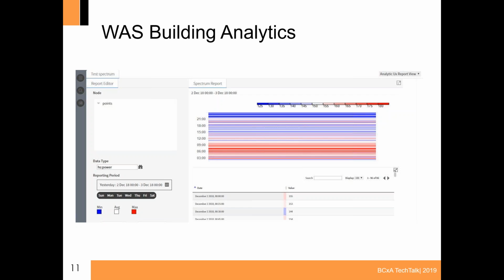And he pulled up another screen. Nope, they didn't override the system. All right. And I went from this screen. Unfortunately, I don't have screen captures for the other, but went through and said, show me output temperatures from the heat pumps versus room temperature and a few other things. And lo and behold, it appeared very much like the building wasn't being set back.